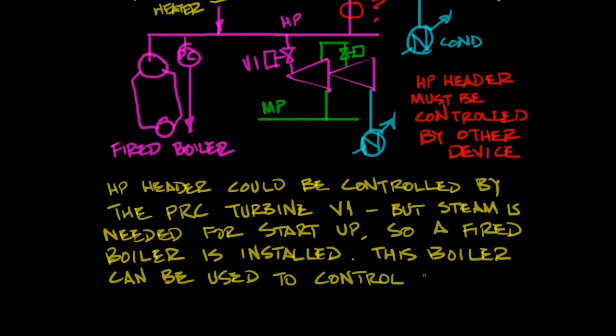But the steam is needed for startup because there won't be any steam prior to starting up the furnaces because until you have feed going through the furnace you won't have any heat at the quench exchanger to produce the steam that supplies the SHP header. You need some kind of steam to get the turbines running prior to starting the furnaces.